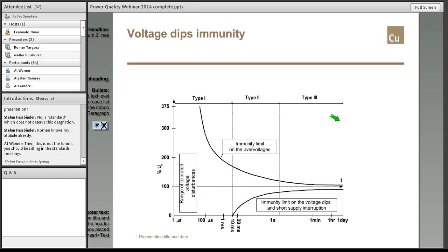Next slide is about a curve showing compatibility, and we've got 3 types, let's say, of events. We've got the immunity limit for voltage dips and supply interruptions, and the range of tolerance. And we've got type 3, which is from 2 seconds up, of very short voltage variation. Then we've got mostly voltage dips and sags with a duration between, I think, half cycle to 2 seconds, and we've got, let's say, temporary spikes, or very short term but very high magnitude events, which are type 1.